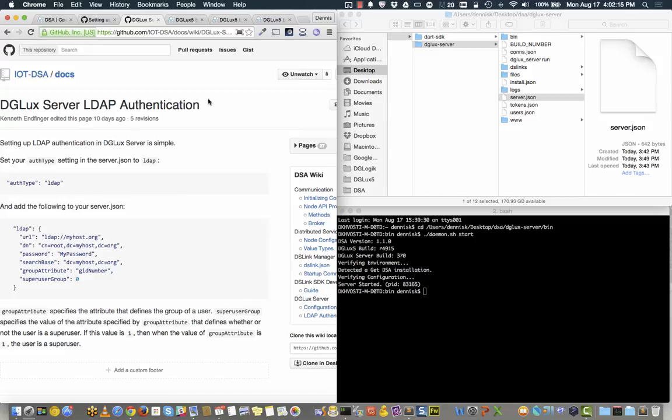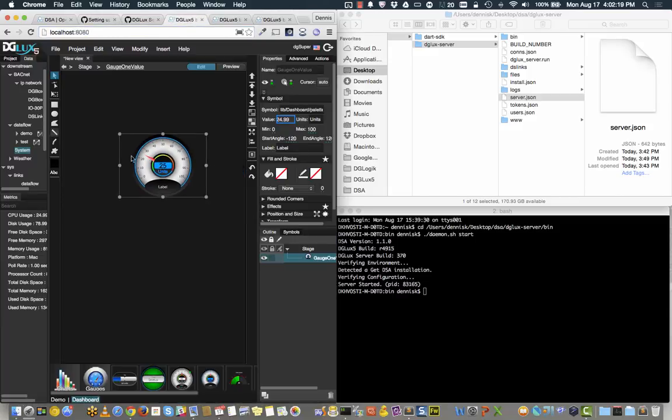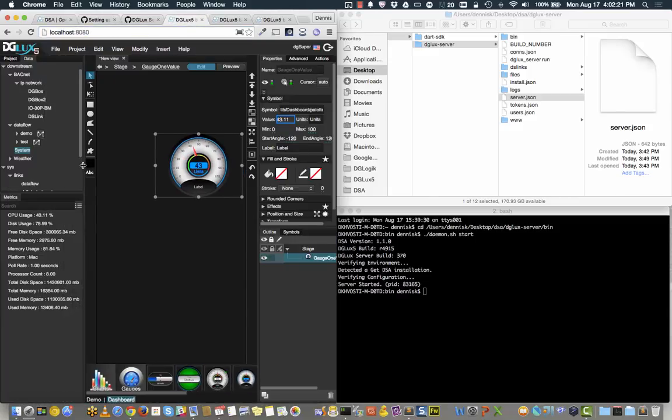And the final aspect of your installation I'd like to show you is we've already explored downstream. So downstream is all the connections to our server from the DS links. In this case, the DS links are actually running locally on our computer. However, the BACnet DS link, Modbus, any other, as we call a microservice, can actually run on any other machine or physical hardware and literally just connect to your broker and make that available to you.